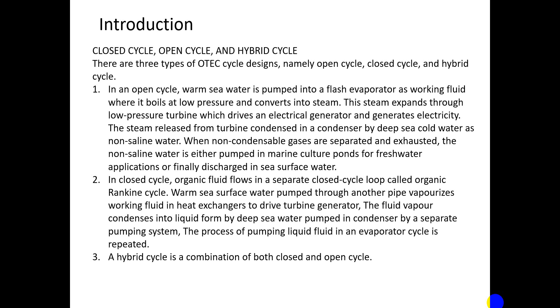In case of the open cycle, this warm sea water is pumped into the flash evaporator as the working fluid, where it boils at low pressure and converts into steam. This steam expands through a low pressure turbine, which drives an electric generator and generates electricity. The steam released from the turbine is condensed in a condenser using deep sea cold water, producing non-saline water. This non-saline water is either pumped into marine culture ponds, used for fresh water applications, or discharged back into the sea.